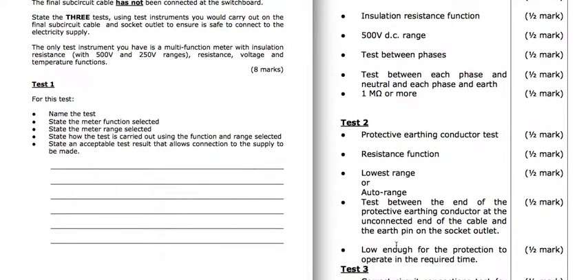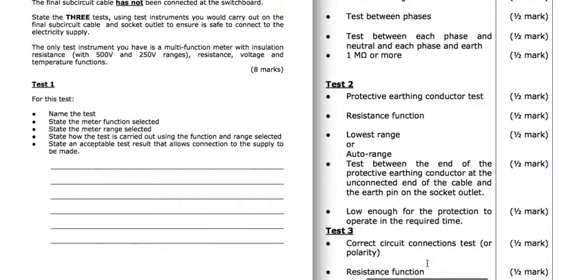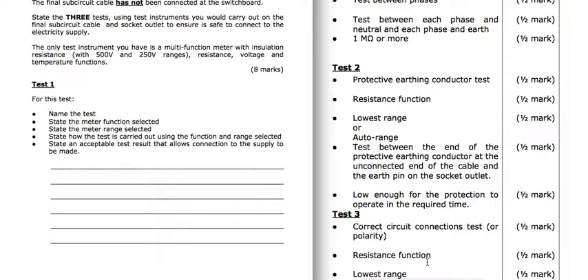For our second test here, with the protective earthing conductor, we're looking for resistance, a low ohms range. Test between the end of the protective earthing conductor at the unconnected end of the cable and the earth pin on the socket outlet. And we need a resistance that's low enough for the protection to operate in the required time.